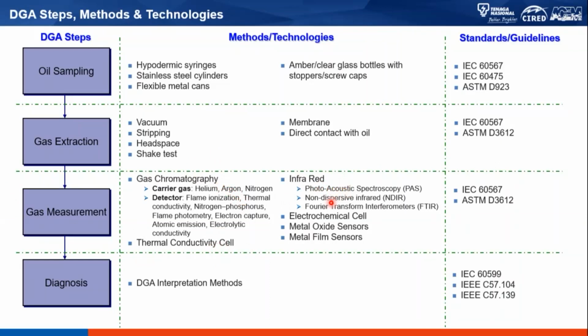Those are photoacoustic spectroscopy, or PAS, non-dispersive infrared, or NDIR, and Fourier transform interferometers, or FTIR. These are based on infrared technology, whereby the molecules of these gases are heated up by infrared, and with the help of a filter, this infrared can be measured or detected in terms of the type of gas being analyzed within the unit.